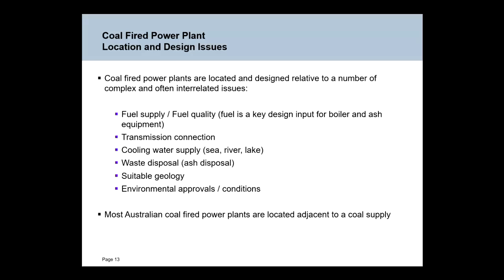First thing is fuel. Because the fuel is coal, and coal is a rock, it changes quite dramatically from area to area, and even within a nominal area, in its combustion characteristics. So you have to know what fuel you're going to burn when you design your power station. The boiler, the ash handling, the flue gas handling, all change depending on the characteristics of the fuel.